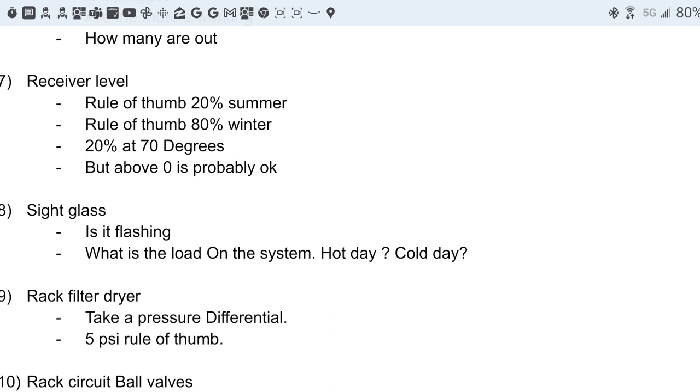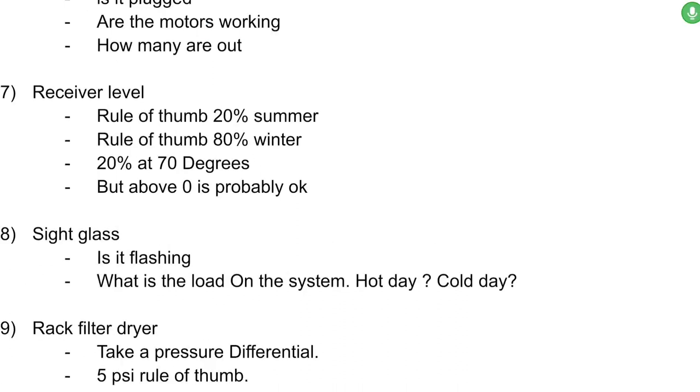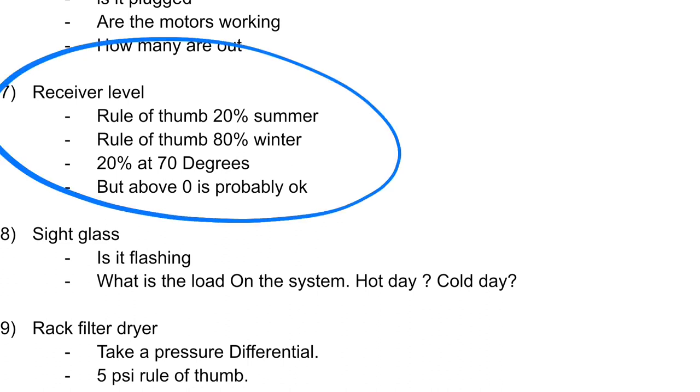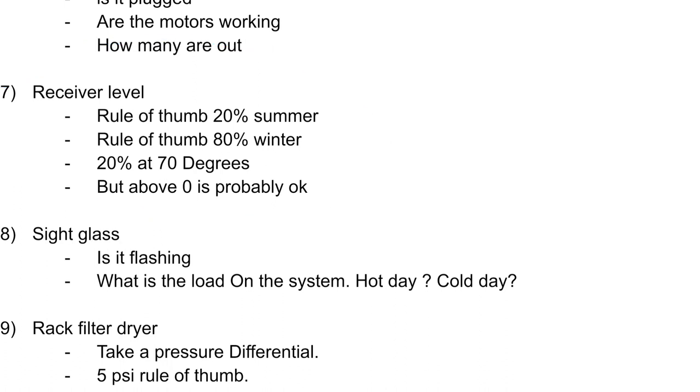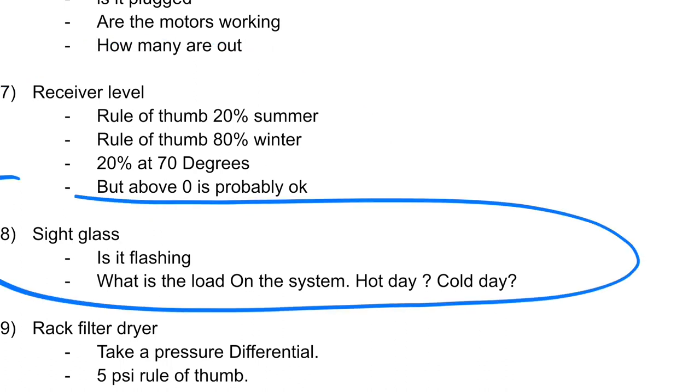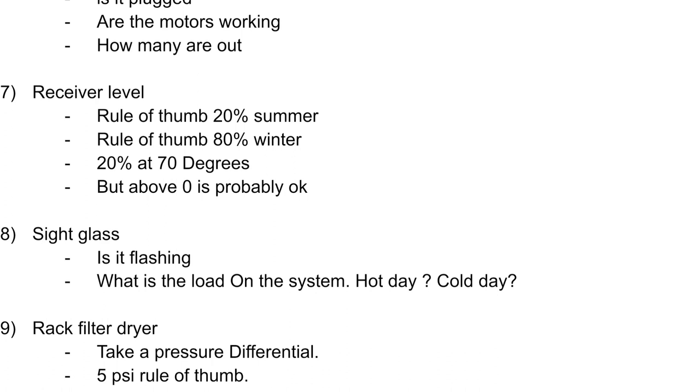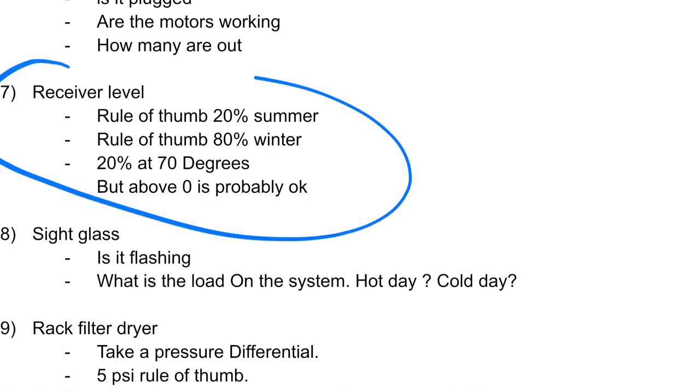And then next up is receiver level. Low refrigerant is probably one of the number one causes of service calls, leaks and leak repair. That's the number one thing. So receiver level is super important. Now, when I was a wee little technician, I used to think that I could get away with just looking at the sight glass alone. You can't. You have to look at the receiver level.